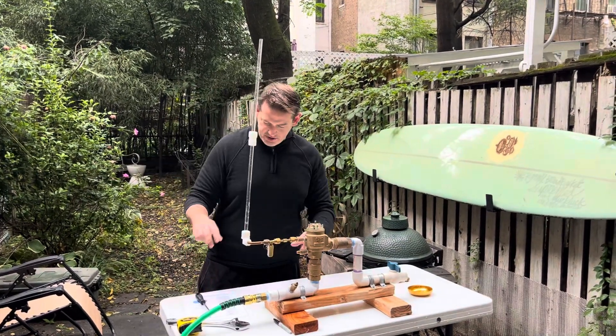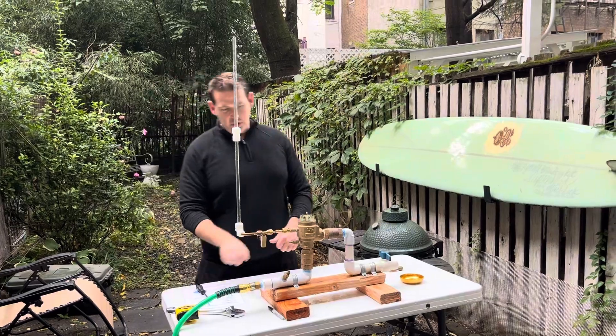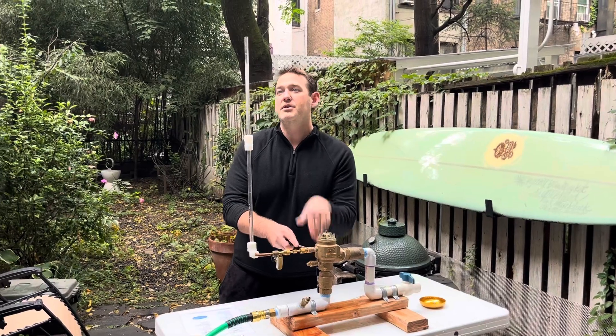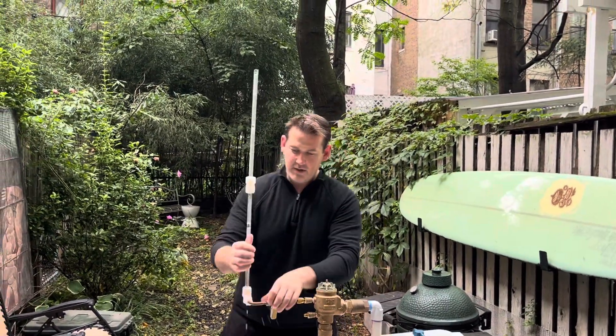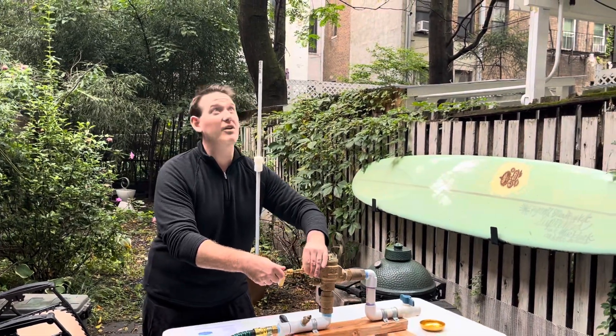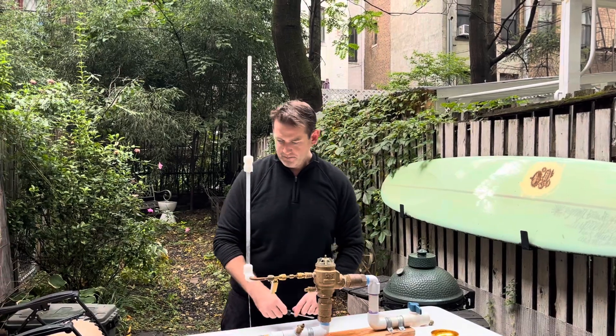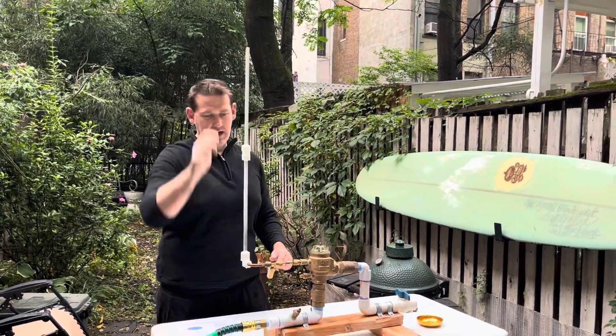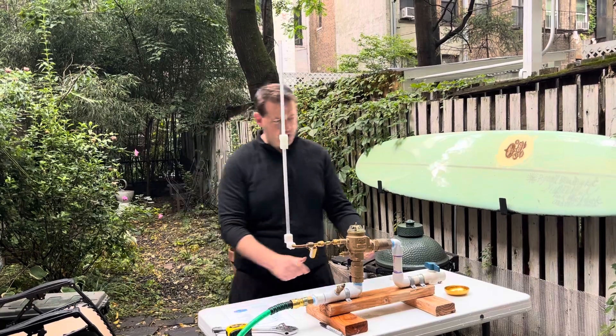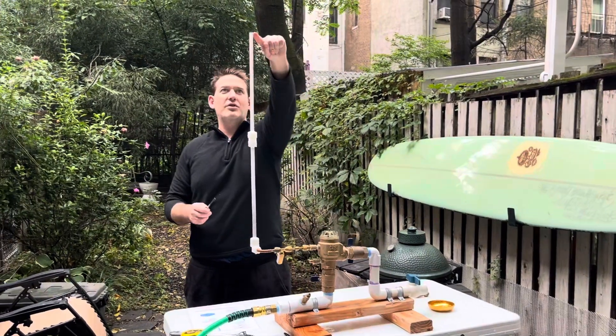The top of the water column has to be at least 27 and three-quarter inches above the air inlet. Open test cock two slightly to fill the water column all the way to the top — you have to make sure all the fittings are very tight, otherwise the sight tube will leak. Once the water is all the way to the top, close test cock two, close shut off two, then close shut off one.